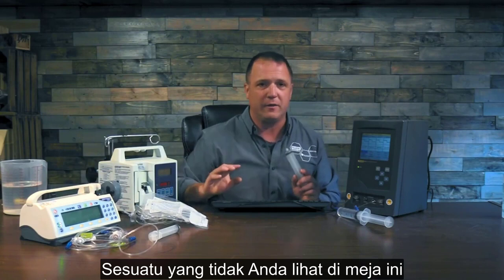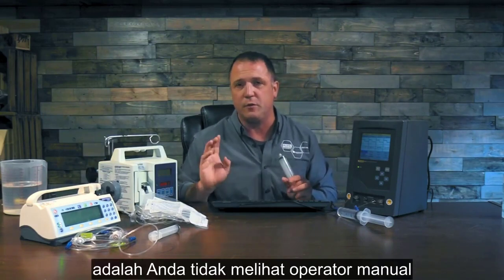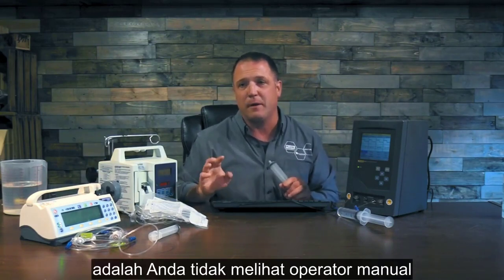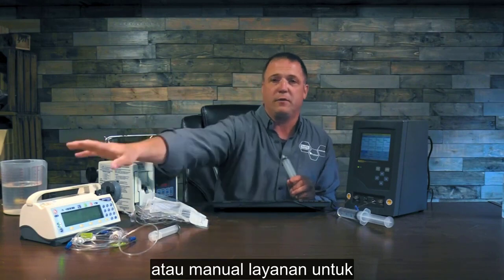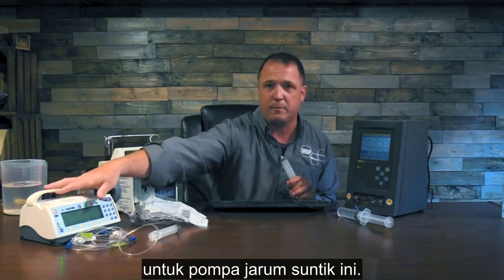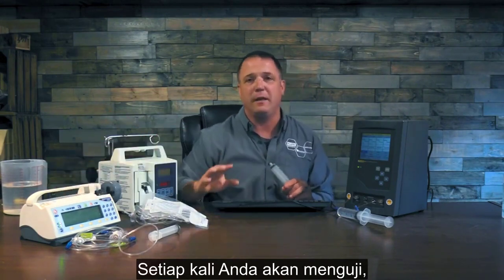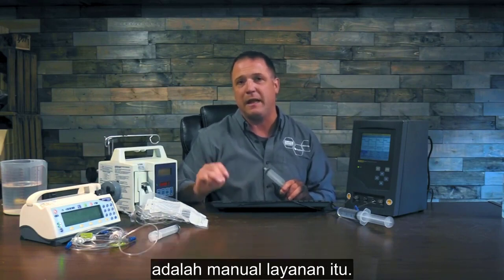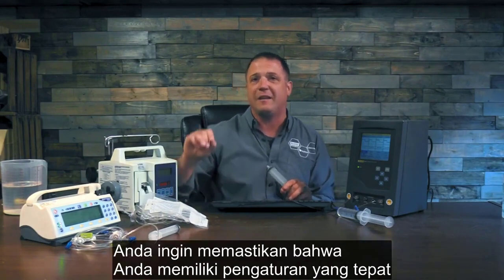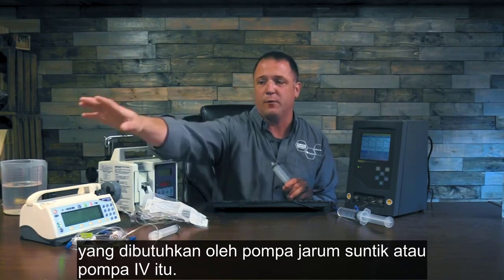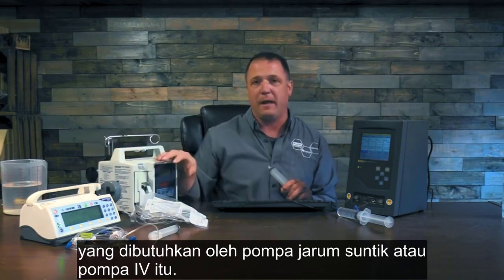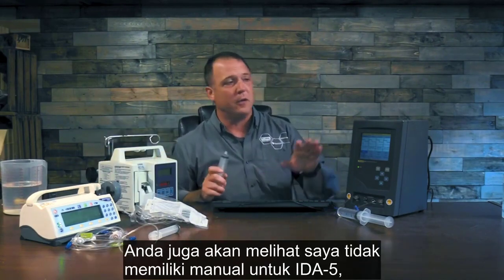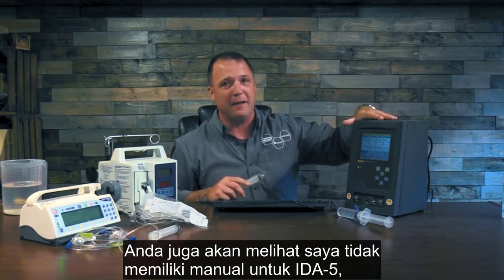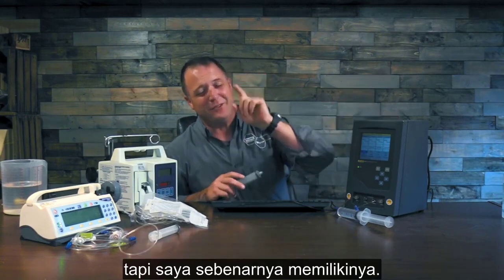Something that you don't see on this desk, and there's a reason for it, is you do not see the operator's manual or the service manual for this syringe pump. Anytime you're going to test, the other thing you should have on your bench is that service manual. You want to make sure that you have the exact setup that it calls for in that syringe pump or that IV pump. You also notice I don't have the manual for the IDA-5, but I actually do.